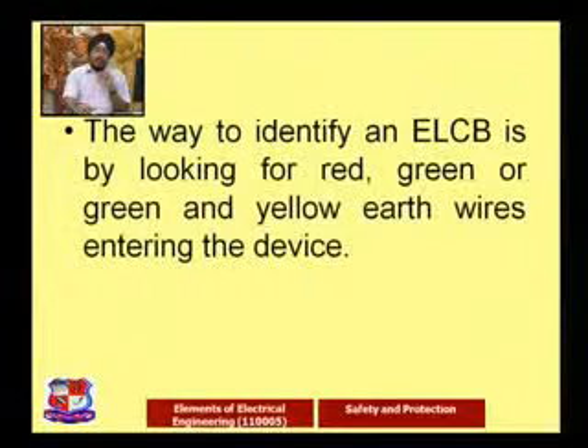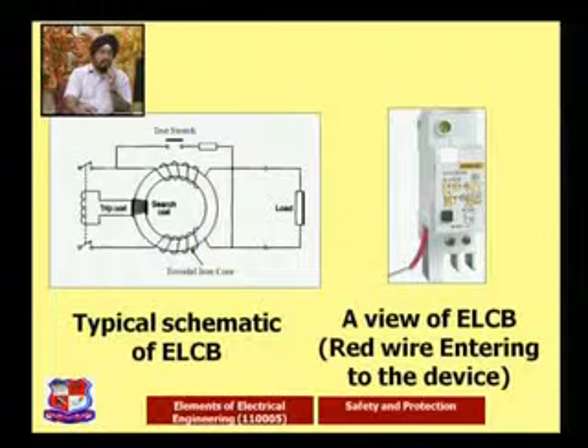How to identify the ELCB? The wire going inside the ELCB is thin, because the earth wire system is there. One way to detect it is that it may be a red wire, green wire, or a green and yellow earth wire combination that enters into the device. We'll go with the current ELCB.